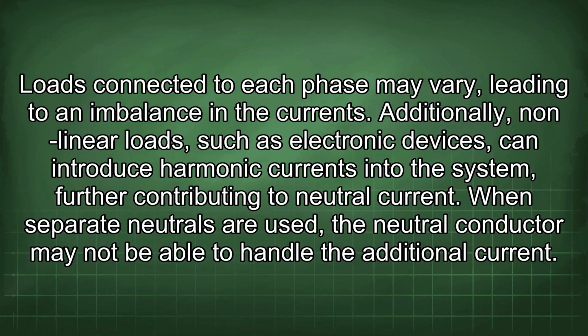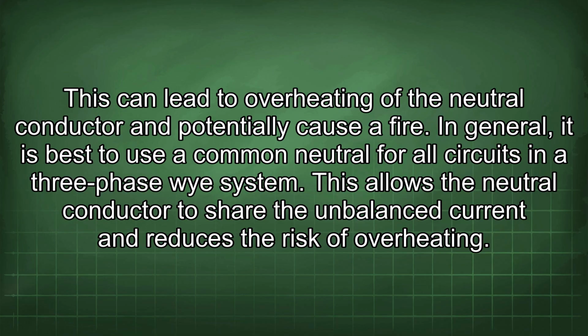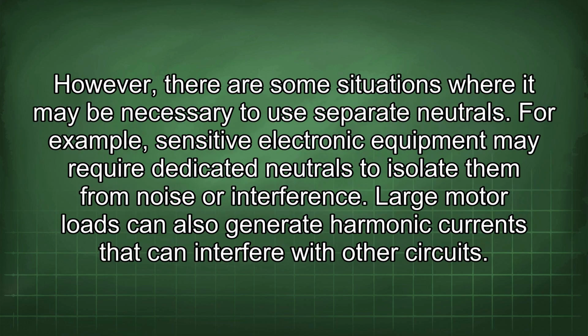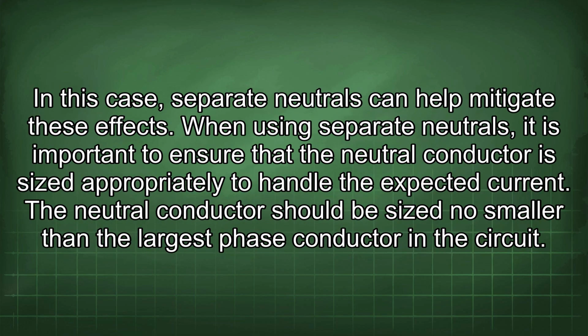When separate neutrals are used, the neutral conductor may not be able to handle the additional current. This can lead to overheating of the neutral conductor and potentially cause a fire. In general, it is best to use a common neutral for all circuits in a three-phase Y system. This allows the neutral conductor to share the unbalanced current and reduces the risk of overheating. However, there are some situations where it may be necessary to use separate neutrals. For example, sensitive electronic equipment may require dedicated neutrals to isolate them from noise or interference. Large motor loads can also generate harmonic currents that can interfere with other circuits. In this case, separate neutrals can help mitigate these effects.